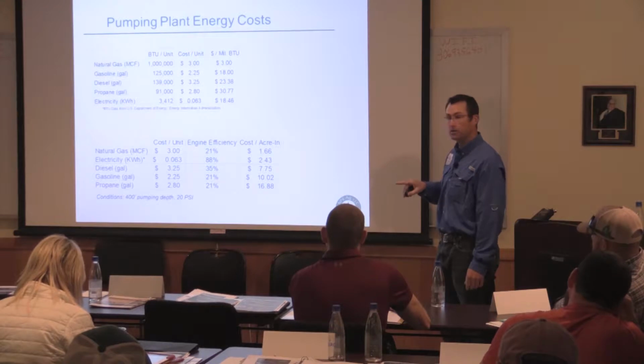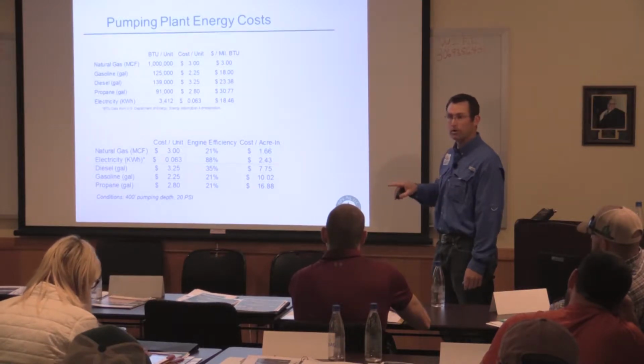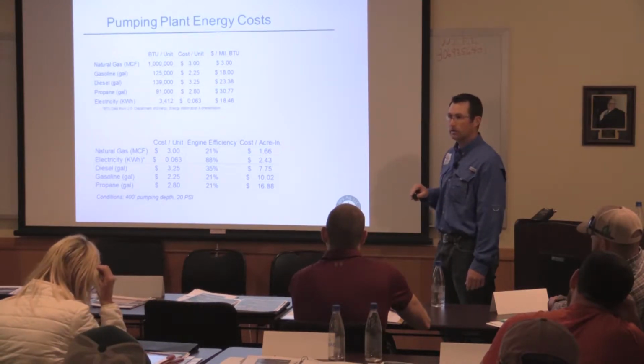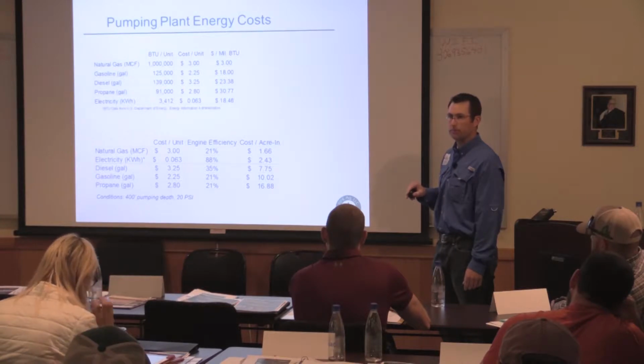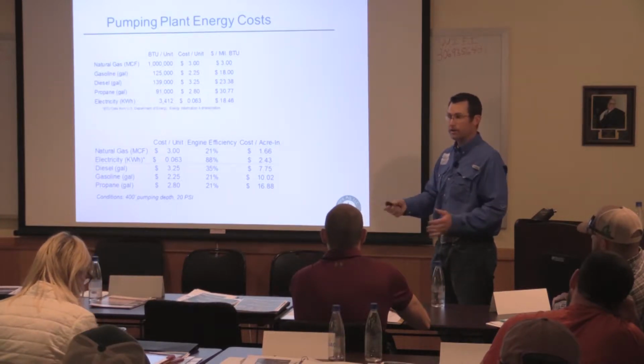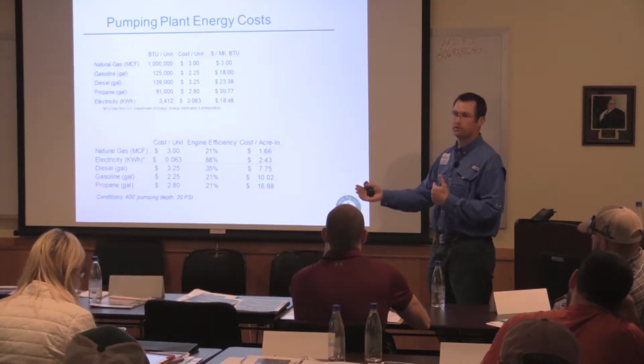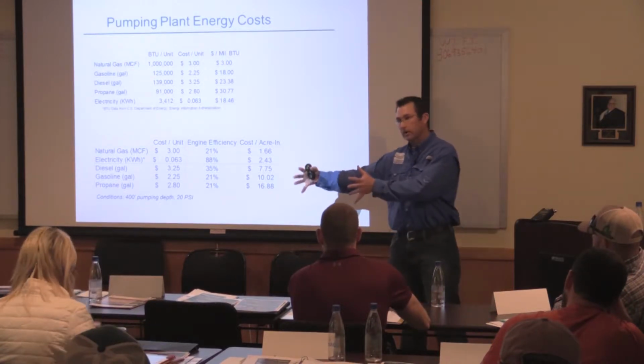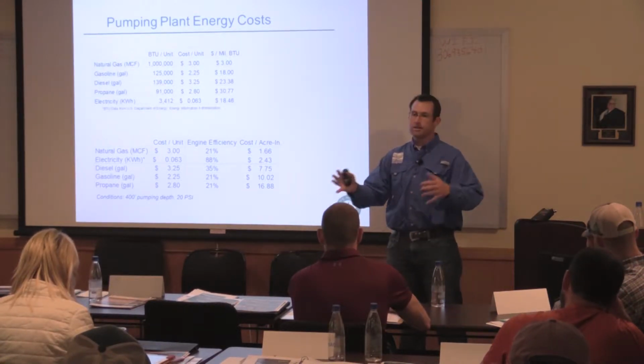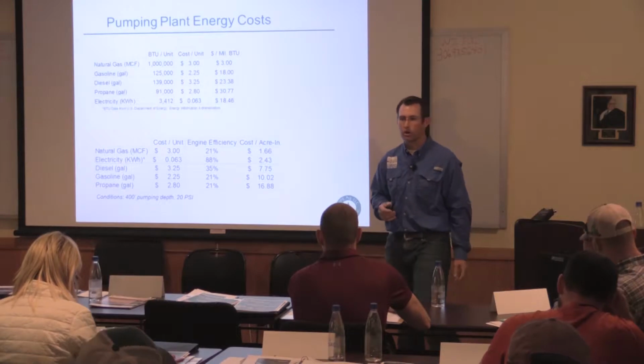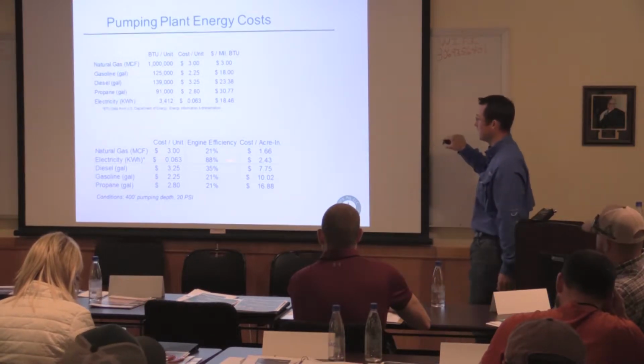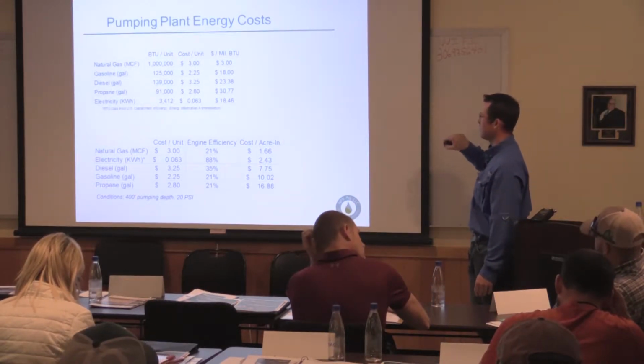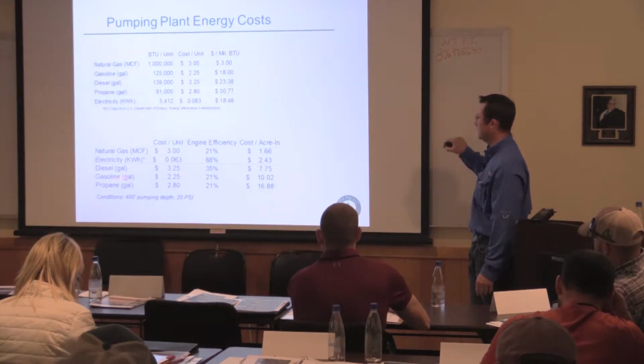If you're buying a new electrical motor, a vertical hollow shaft motor, you're going to have to buy an inverter duty premium motor — it's not available any other way. That change happened about 18 months to 2 years ago, and there was enough backstock that guys were trying to get the cheaper motor, but it's just not an option anymore. So with a vertical hollow shaft motor, you're going to get much higher efficiency, and you'll see how that plays in — it's a big benefit to you.